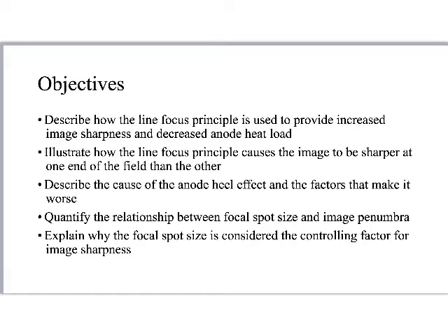So it does two things: it allows us to decrease the heat load to the anode and improves image sharpness. It's not a perfect solution, but it's pretty good. We'll talk about some of its imperfections, like how the line focus principle causes the image to be sharper at one end of the field versus the other. I've already had some student questions about that. That is not to be confused with the anode heel effect — that is a shortcoming of the line focus principle as we use it in the x-ray tube.